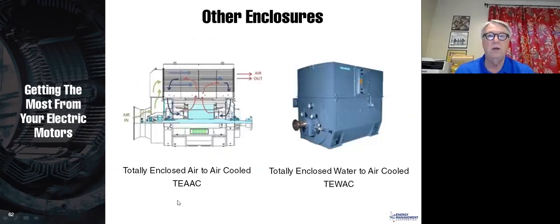This is a totally enclosed air-to-air cooled. Now we're getting into some fancy stuff. You've actually got an air-to-air heat exchanger on there, and you're using a separate fan in order to use that heat exchanger to cool motors. Or if you don't want to use an air-to-air heat exchanger, you can use a water-to-air heat exchanger. And so this would be a totally enclosed water-to-air cooled. This way, in both of these cases, the motor stays very, very clean and is good for dirty environments.